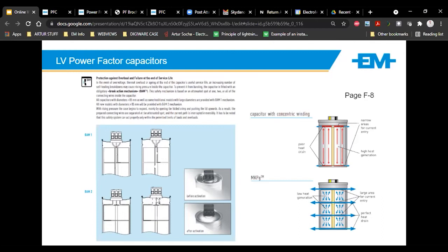So historically, people are quite scared of PFC systems. They have had fires before. Historically, manufacturers used plastic casings. They've moved away from plastic to steel. On these type of systems, I haven't had any fires. Plastic, yes, there's been fires. It happens because of wear and tear, and the internal disconnection doesn't work properly. It fails, the unit ignites internally and starts melting.